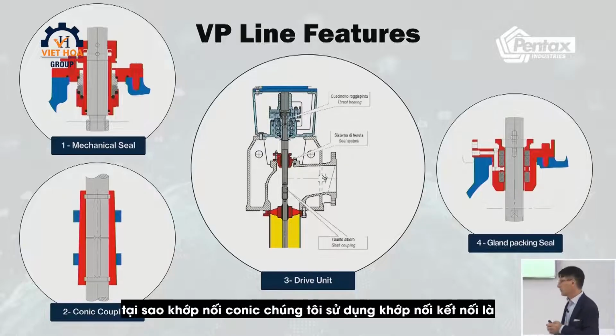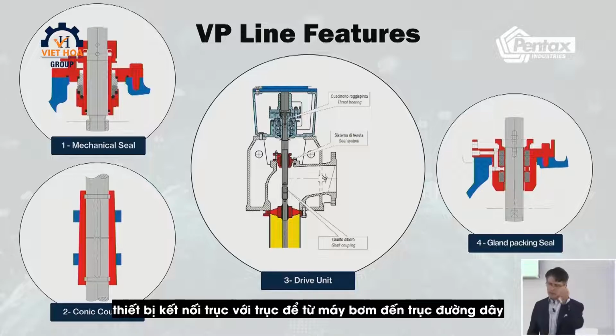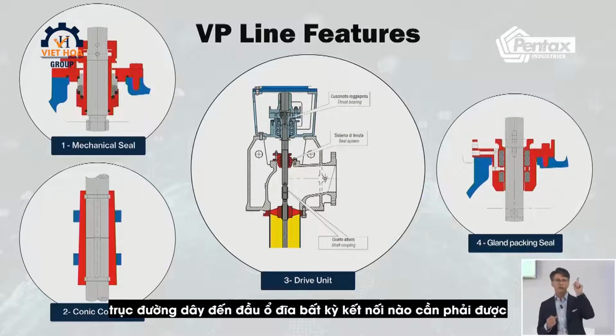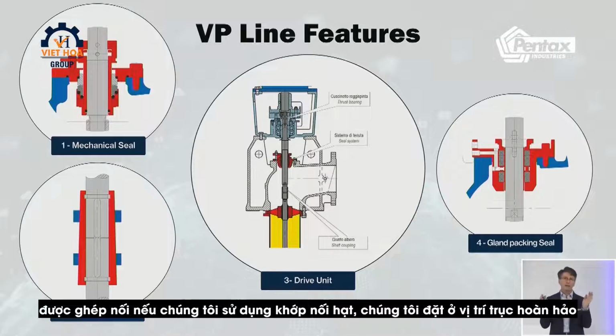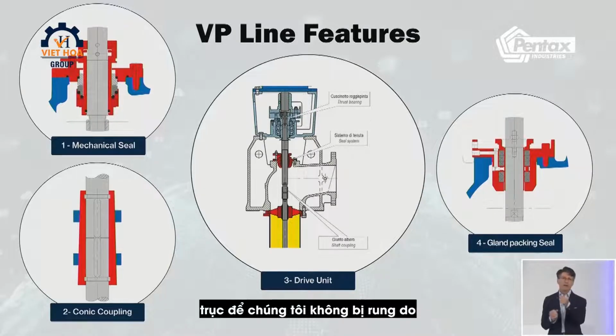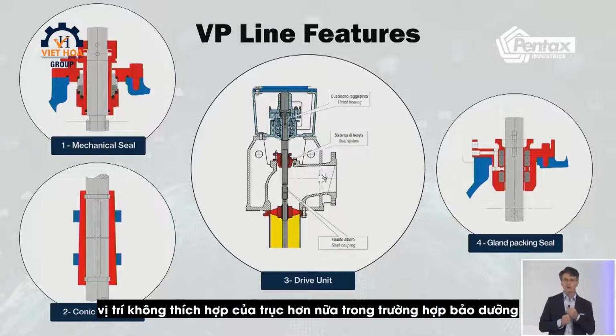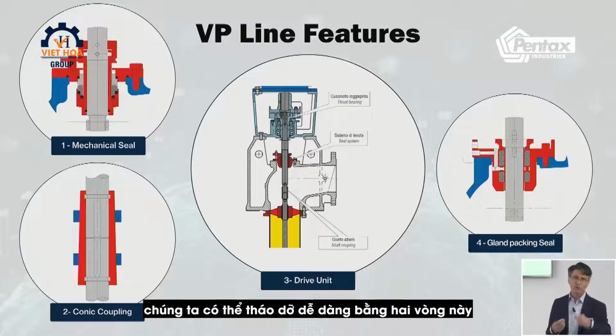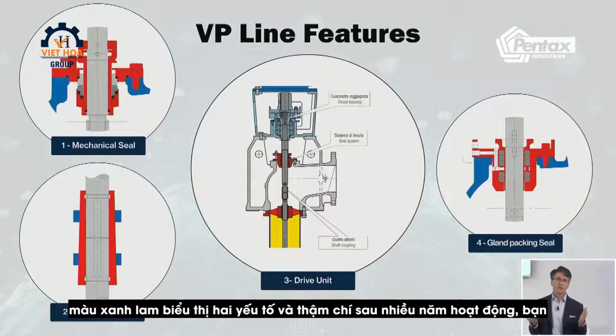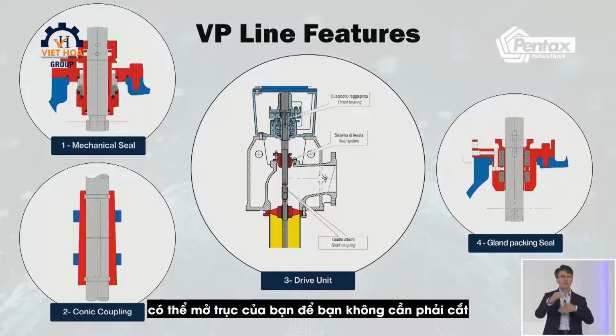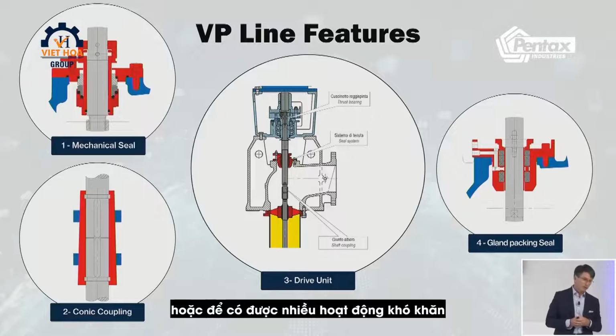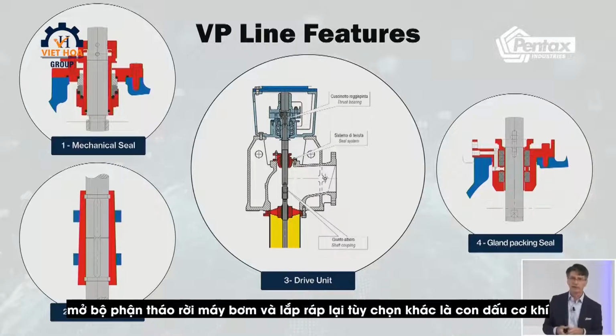Why conic coupling we use? The conic coupling is the device which connects shaft to shaft, so from the pump to the line shaft to the drive head. Any connection needs to be coupled. If we use conic coupling, we put the shaft in the perfect axial position, so we do not have vibration due to the non-proper position of the shaft. Moreover, in case of servicing, we can dismantle easily by these 2 rings, the blue rings, the 2 elements, and even after many years of operation, you can get your shaft open, so you don't need to cut or do a lot of difficult operation to open the pump, disassemble, and reassemble.